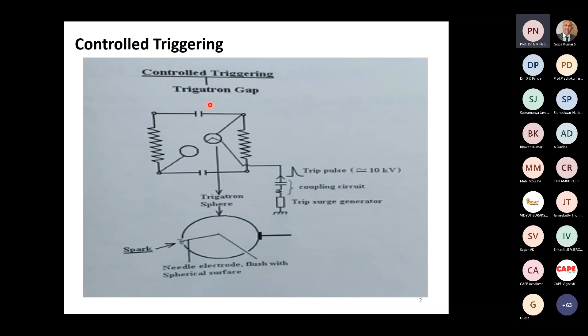Here there is a charged capacitor. There you have got a cloud. Here there's a ground electrode and a needle electrode. They have got the ESE rod. But again, if you increase the spacing slightly, even though the field is constant, 200 kV is still there all the time. Whatever spark you apply here, it will not cause flashover here. So we see that the ESE rod has got its limitations, which is proved by this very, very simple device, which is used day in and day out in high voltage laboratories all over the world. This is known as a trigatron gap.